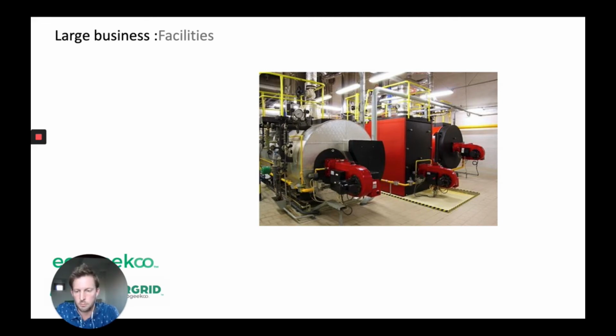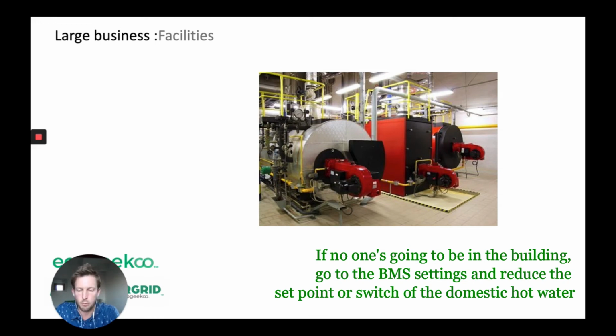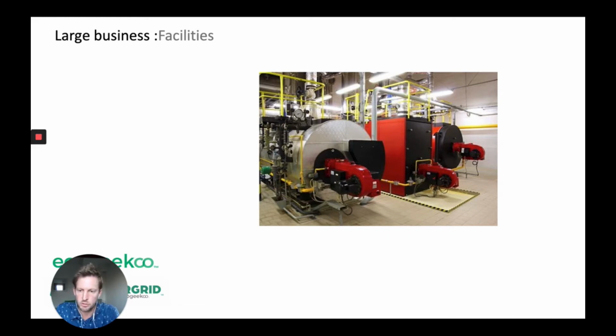So what you might want to do is get on the BMS system and reduce the set point or switch off the domestic hot water. It's often these very large gas boilers can be running just to provide a bit of hot water to some hand basins. And if your building is fully vacated, there's no sense in keeping them active. There's a very big CO2 profile associated with these, and a lot of gas is consumed just keeping all those miles of pipework and water hot just for a hand basin on the 15th floor. So my advice is to work again with your controls engineer to figure out the best way to isolate and switch off your domestic hot water system.